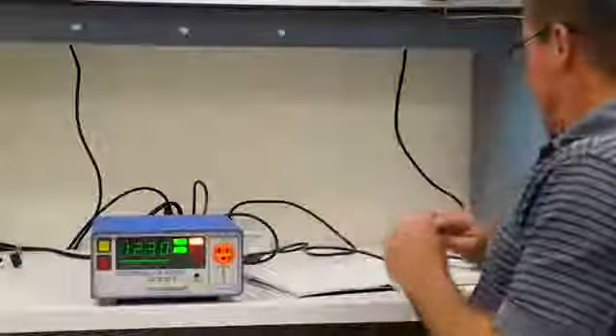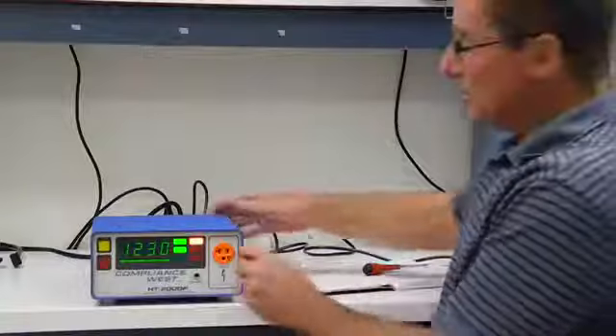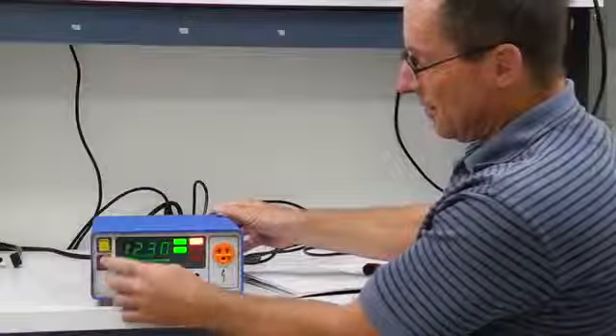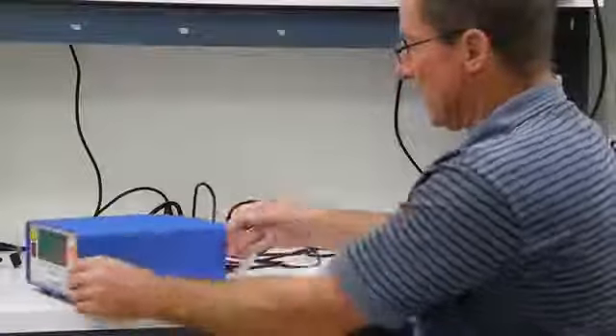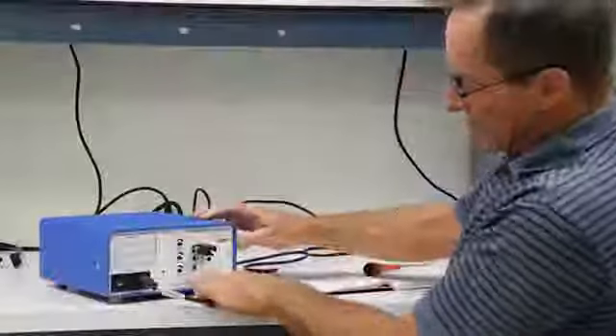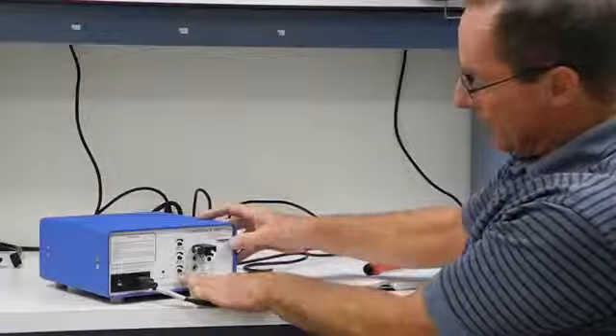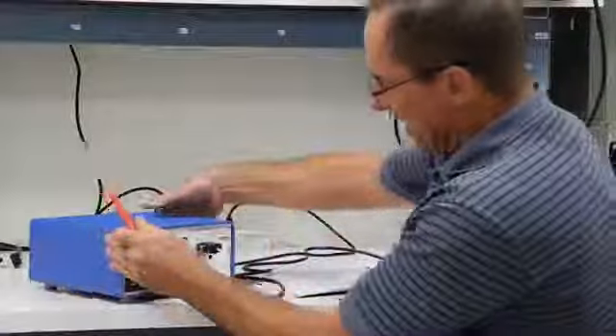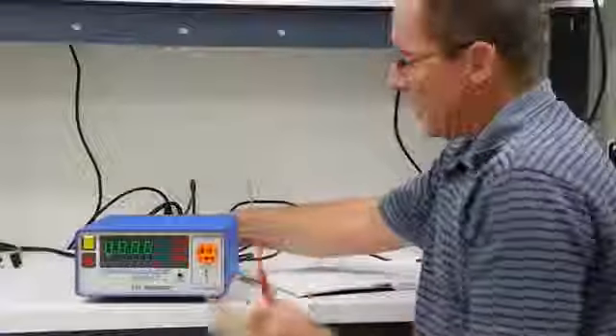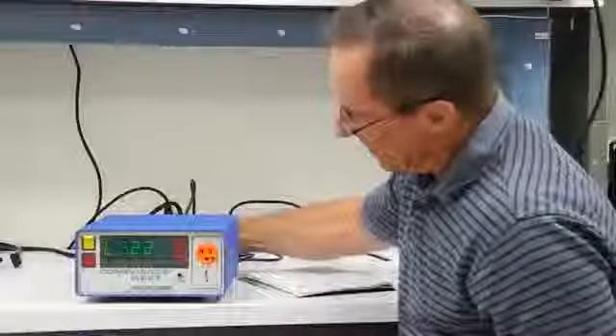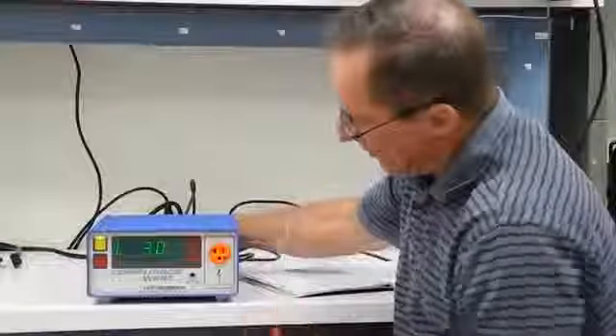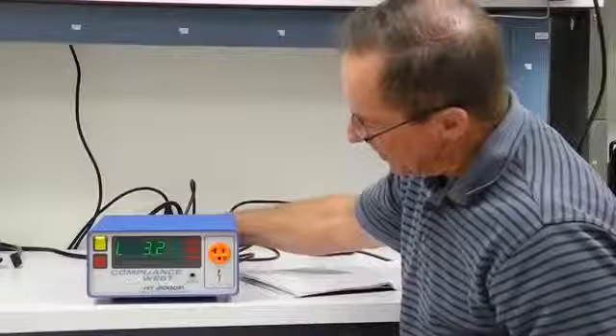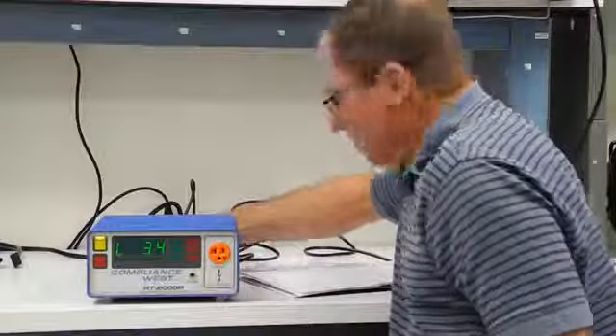Okay, the next thing we're going to do is set the trip current for 2 mils. Turn it off. We don't need to have it running. The trip current is down here at the bottom. It's called leakage limit. And you do that by turning the knob. On the front panel, as you turn the knob, you'll see the leakage current show up. That's the leakage current limit. So what we want to do is set it for 2 milliamps.